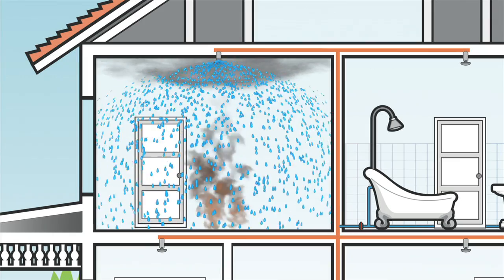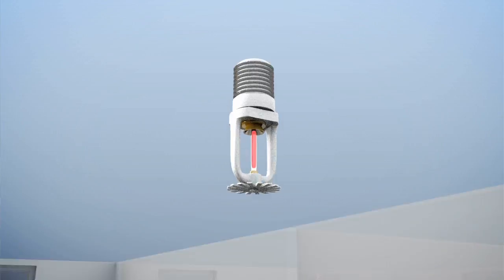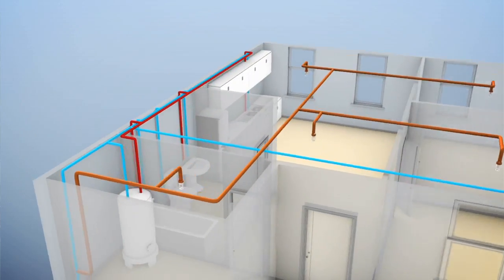In terms of water demand, there is no impact of sprinkler systems on water demand. When the sprinkler systems go off, in most cases it wouldn't affect the system at all. The flow is between 15 and 25 gallons per minute — nothing more than what you'd see on the fixture count of an average home. That allows us to tie it into the domestic system and make it an extension of the existing plumbing system.